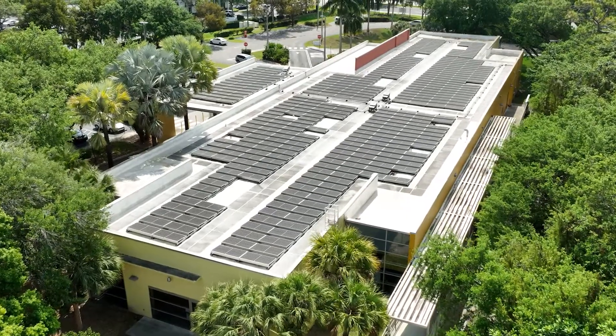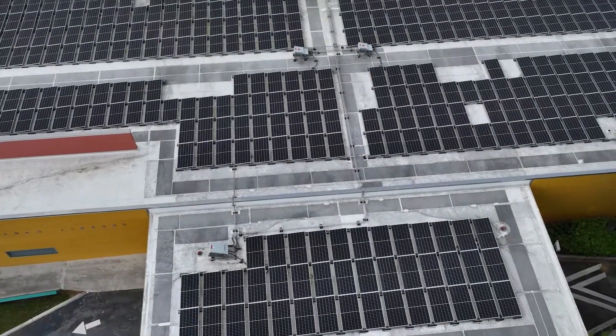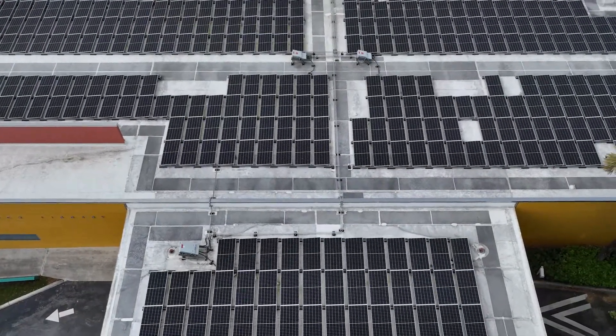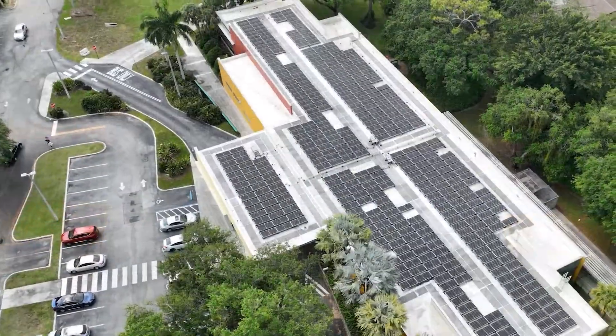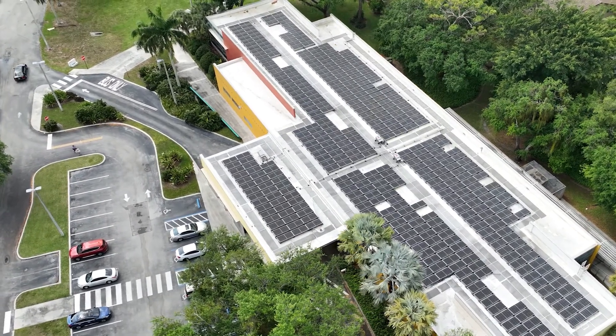The roof and the solar both now have a 25-year lifespan, so we have alignment between the expected life expectancy of the roof system and the life expectancy of the solar. One of the things we always try to avoid is putting a solar asset on an aging roof asset — we look for alignment. Doing them at the same time brings us that alignment and allows us to look at something on a 25-year horizon.